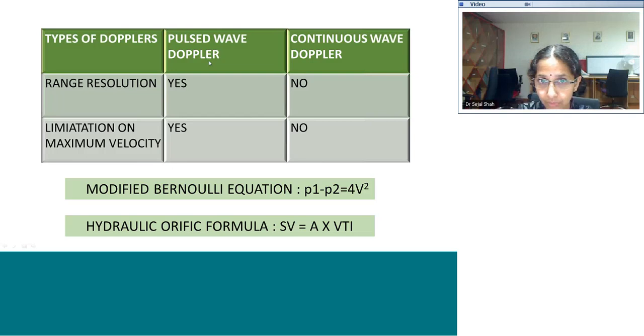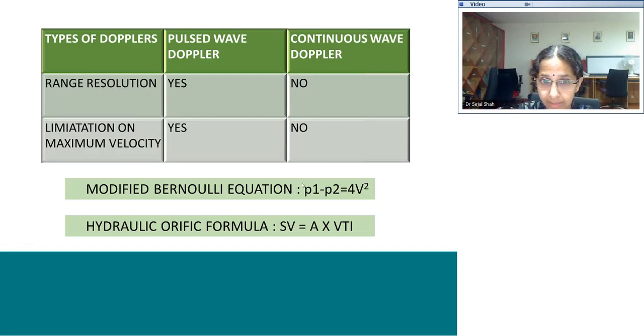There are two types of Dopplers: the pulsed wave and the continuous wave. Pulsed wave Doppler is done at a particular point, whereas continuous wave Doppler picks up all signals across that line. Pulsed wave Doppler has beautiful range resolution; however, there is a limit to its maximum velocity, usually around 1.5 to 2 meters per second. Continuous wave has no range resolution but no limitation to maximum velocity.